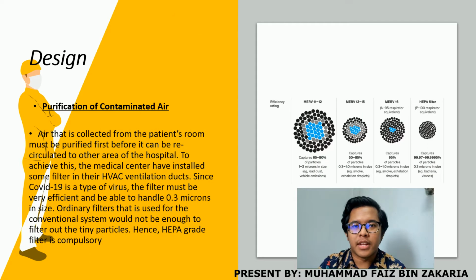Purification of the contaminated air is done before the air collected from the patient room can be released outside the building. This is done by installing a HEPA grade filter in the ducting system.